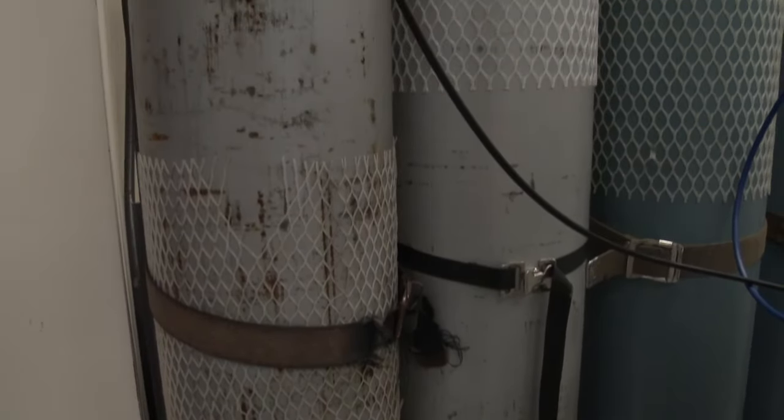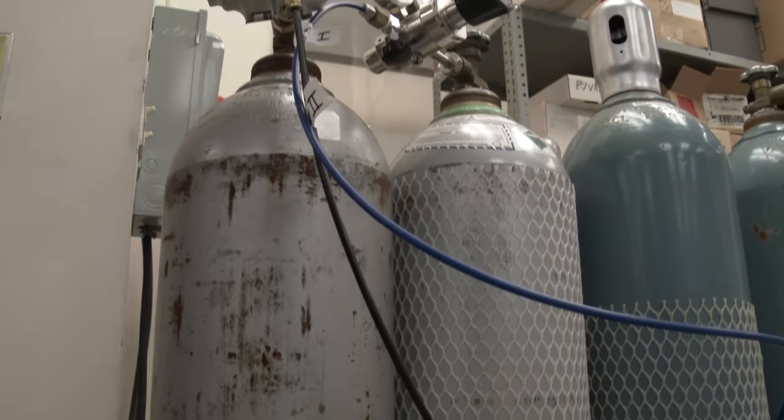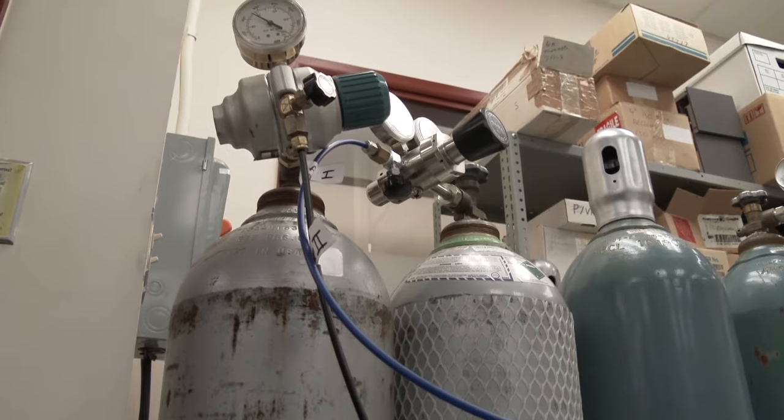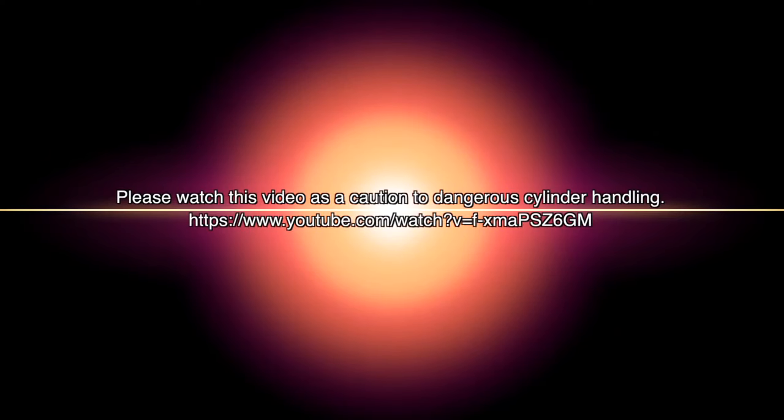Many mass spectrometers, especially electrospray mass spectrometers and GCMS mass spectrometers, also use gases: nitrogen, helium, argon, and hydrogen in some cases. These gases are generally supplied from cylinders. These cylinders are under high pressure, and the gases need to be controlled by gauges and contained within tubing suitable for this high pressure. Please watch this video as a caution to how dangerous cylinder handling can be.